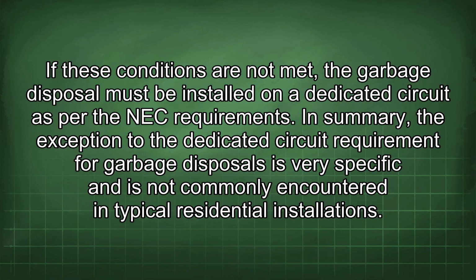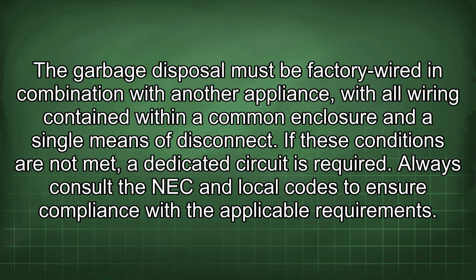In summary, the exception to the dedicated circuit requirement for garbage disposals is very specific and is not commonly encountered in typical residential installations. The garbage disposal must be factory wired in combination with another appliance, with all wiring contained within a common enclosure and a single means of disconnect. If these conditions are not met, a dedicated circuit is required. Always consult the NEC and local codes to ensure compliance with the applicable requirements.